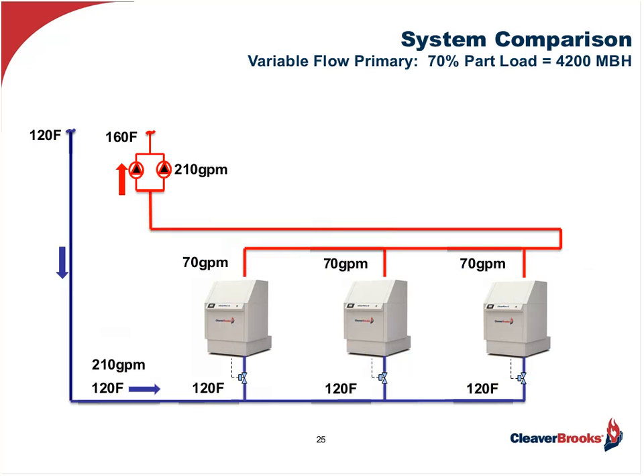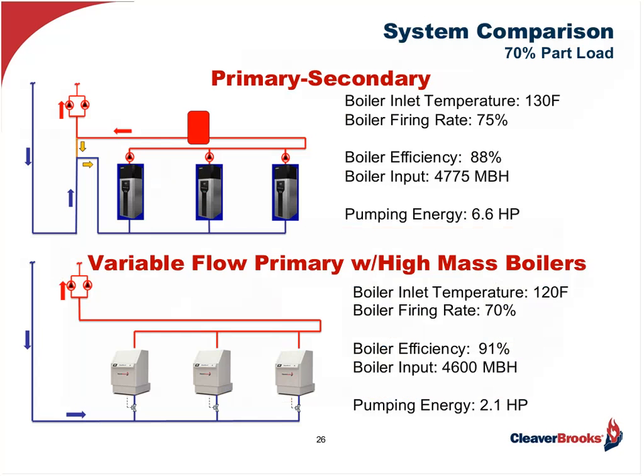And because of that, there's no mixing in the loop. The boilers will see 120 degrees, not the 130 that you see in the primary-secondary. The firing rate will also be slightly less. Now let's compare them and see how they compare. Again, inlet temperature 130 versus 120, firing rate 75 versus 70.